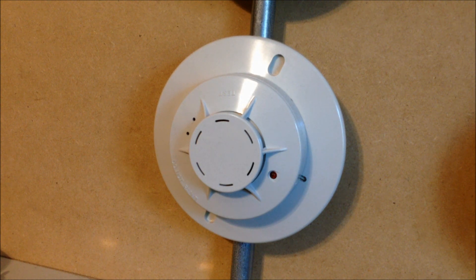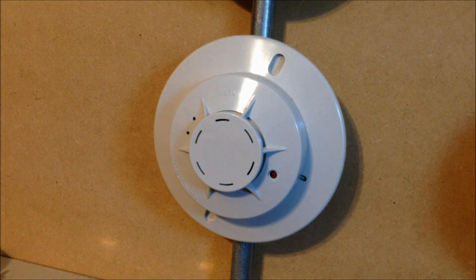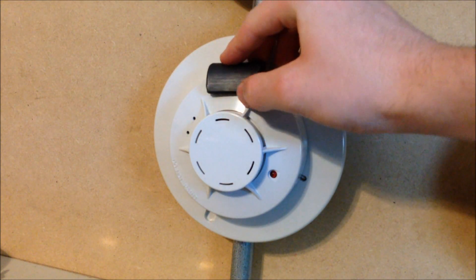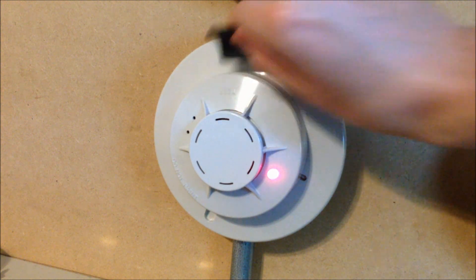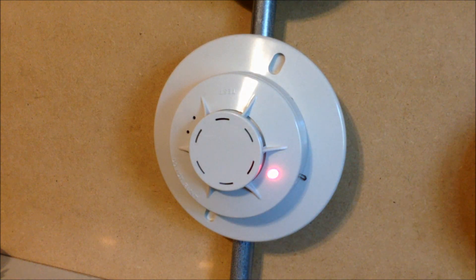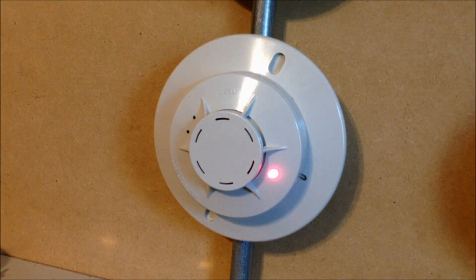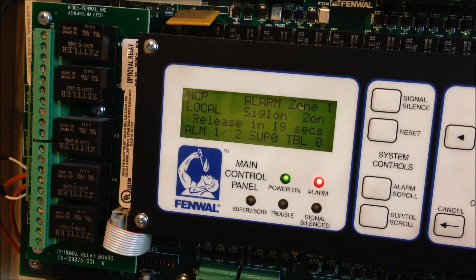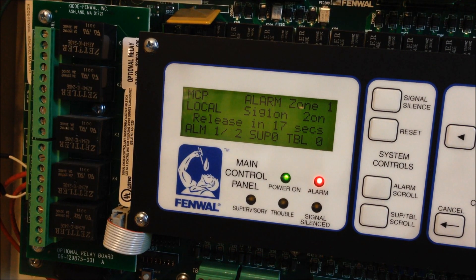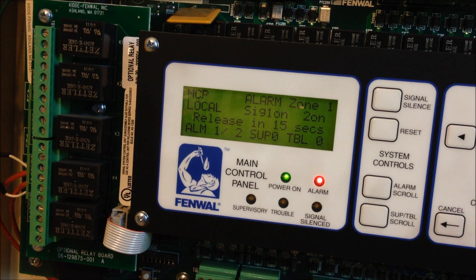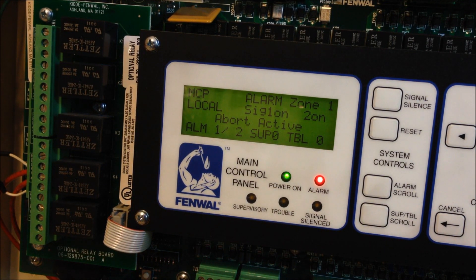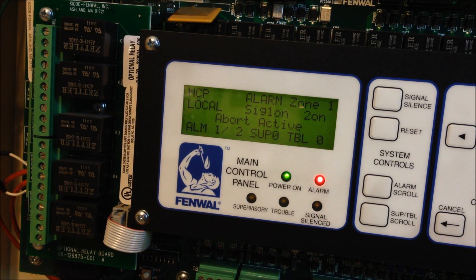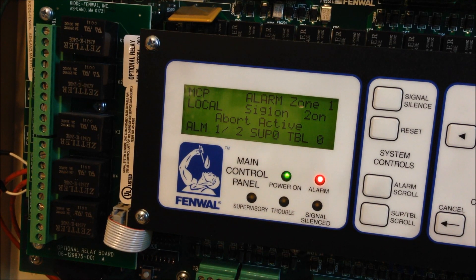Now we're going to activate the CPD-7051 — these are a little more difficult to activate, but there we go, quicker than expected. Now I'm going to go ahead and hold down the abort button. We see 'abort active' on the display and the countdown stops. The system will not discharge the agent while the abort button is held.